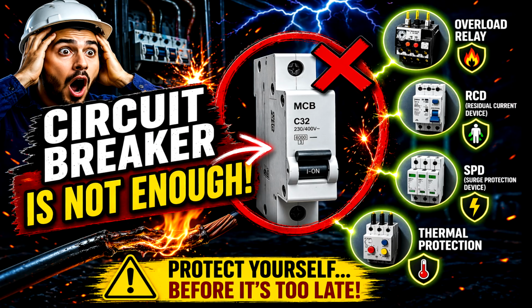Open your eyes. Most electrical fires are not caused by direct short circuits, but by slow overheating plus weak connections. In other words, the real danger starts small, but grows over time. Warning, final thought: if you think a circuit breaker alone is enough, then you're only protecting half the system. Question for you: have you ever seen a melted or overheated wire, even though the breaker did not trip?